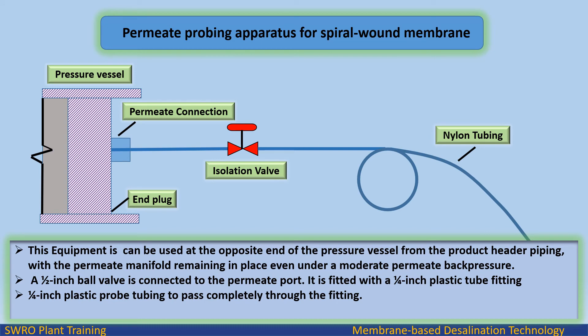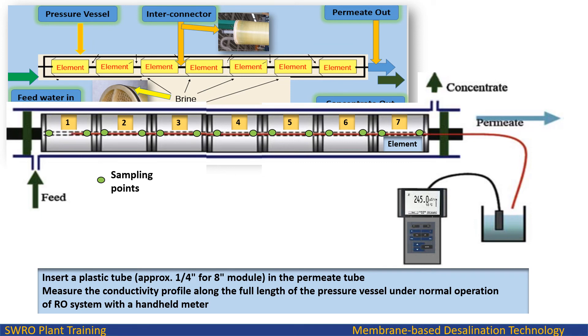This equipment can be used at the opposite end of the pressure vessel from the product header piping, with the permeate manifold remaining in place even under moderate permeate back pressure. A half-inch ball valve is connected to the permeate port and fitted with a ¼-inch plastic tube fitting. A ¼-inch plastic probe tubing is inserted to pass completely through the fitting and into the permeate tube to cover approximately 4 to 8 modules.